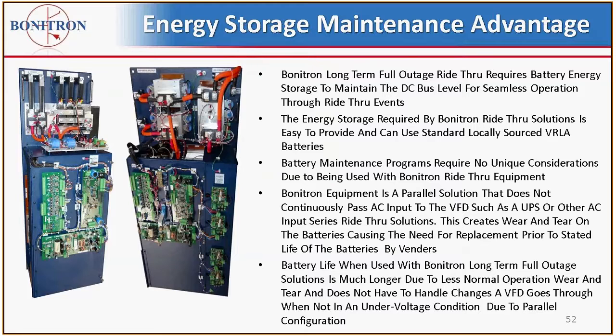So there's venting involved, and then there's also some hazmat issues. And usually with battery energy storage, there will be a maintenance plan that Bonitron does not provide. Usually that's up to the customer to figure out how they want to do their battery maintenance. And in most industrial applications, most plants I've encountered usually have some sort of battery maintenance program. The batteries that we use for the ride-through are standard, so they can fit right into the existing battery maintenance program. There are no special considerations.